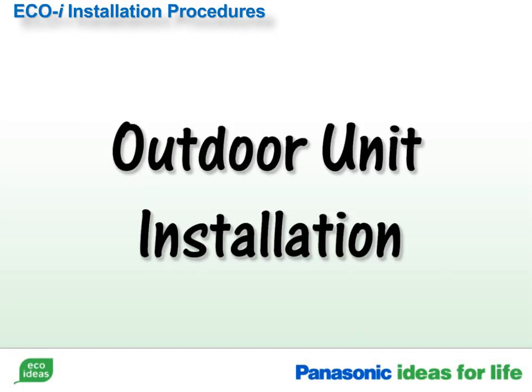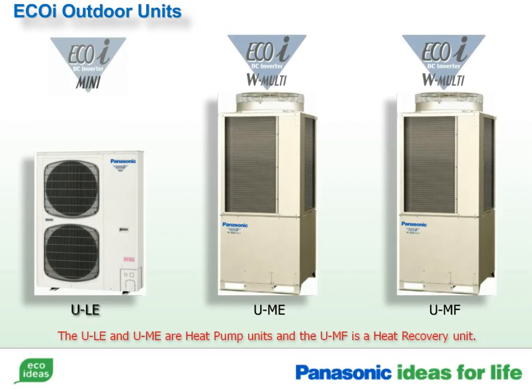Outdoor units and installation procedure. There are several outdoor unit models available at this time. The U-LE and the U-ME are heat pumps. The U-MF is a heat recovery unit that is capable of delivering simultaneous heating and cooling. The U-LE models are 208 to 230 volt single-phase power. The U-ME and the U-MF models are 208 to 230 volt 3-phase power.